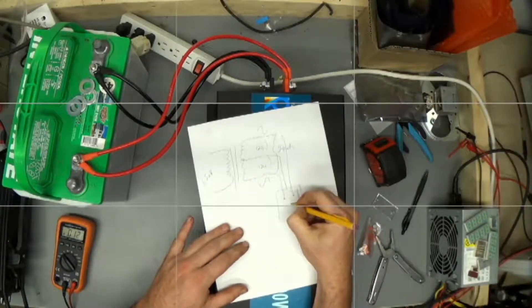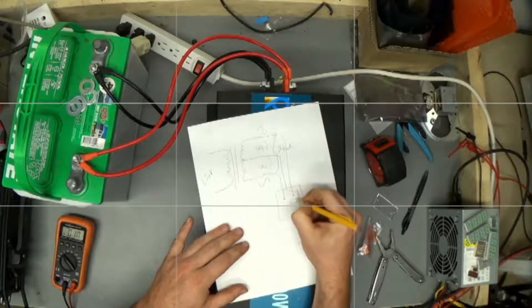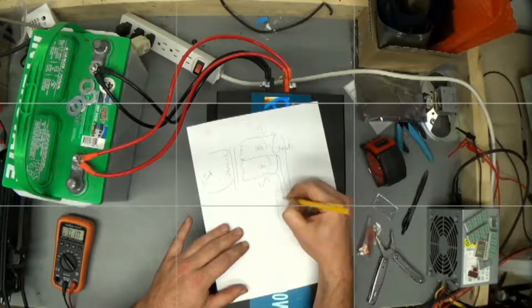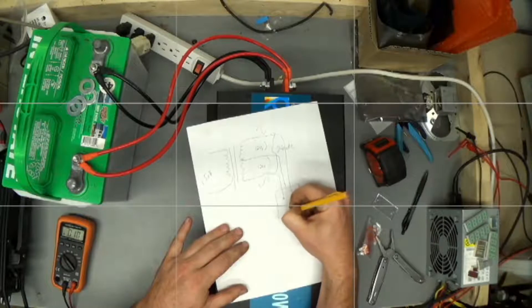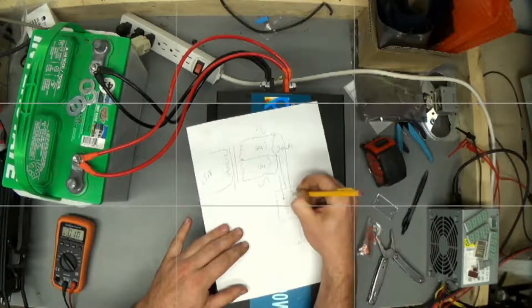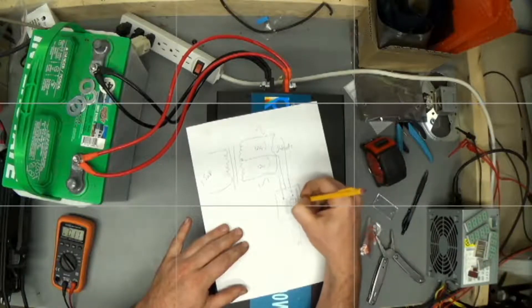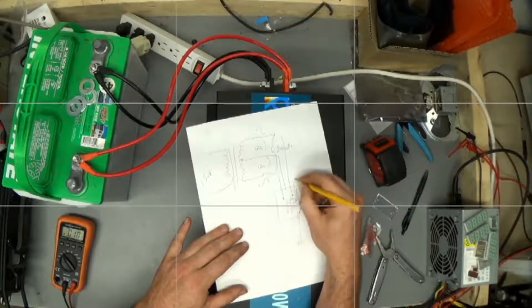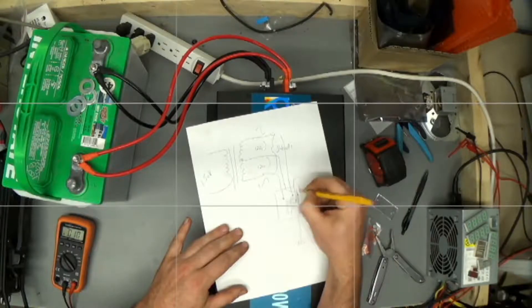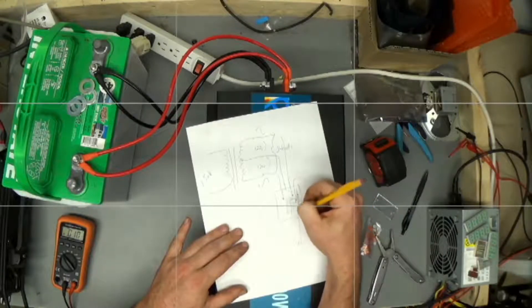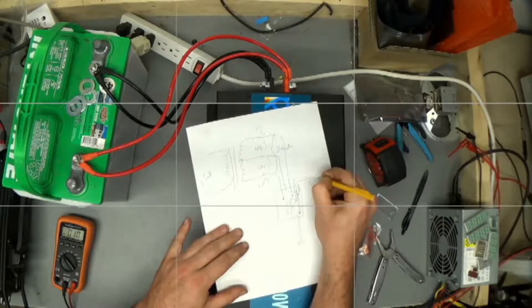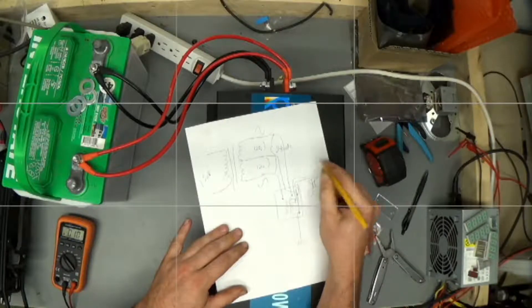And off the bottom of that bus bar, there's a ground wire that comes out and is actually grounded, like to a ground rod, near your service entrance. And then you stick a breaker on here somewhere, and it draws 120 volts off of one of these bus bars. And your Romex, the hot side connects to your breaker and goes out to your circuit. And then a neutral hooks to this ground slash neutral bus bar, and that goes to the rest of your house and powers your light bulbs or whatever.